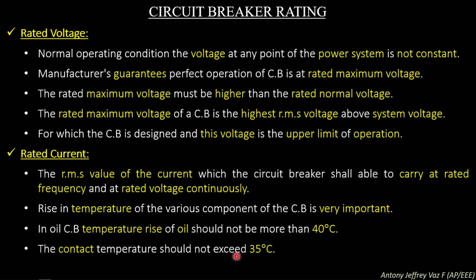In an oil circuit breaker, the temperature rise of oil should not be more than 40 degrees centigrade. The temperature should be less than 40 degrees centigrade so that the oil circuit breaker can work perfectly. Similarly, the contacts of the oil circuit breaker should not exceed 35 degrees centigrade. These two are oil circuit breaker Indian standards. So this standard is followed throughout all the circuit breakers, so that the temperature of oil value and the temperature of contact value should not exceed the standard ratings.